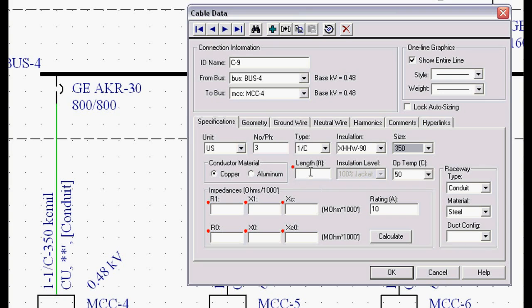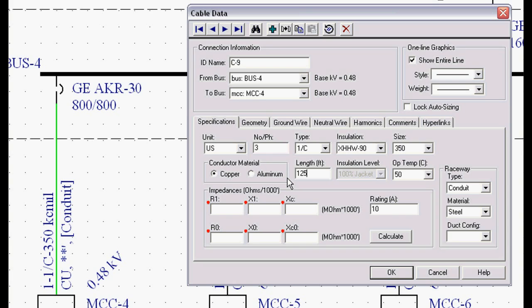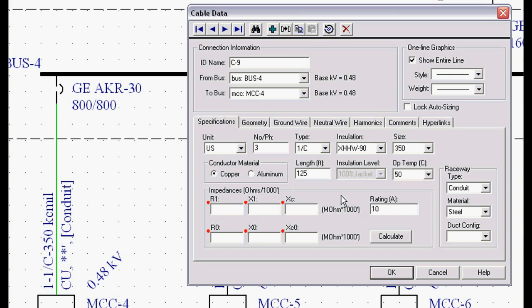The length in feet, we need to know what that is. It shows the little red dot. So we're going to walk that distance off. Typically, in a three-foot step, count the number of steps, multiply by three, account for up, over, and down, any large radius bends.